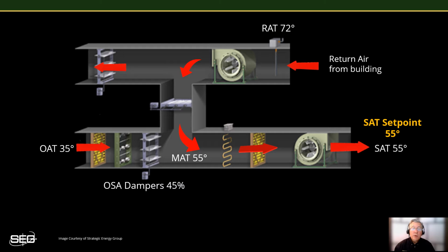And the system is performing properly per command, mixing the right amount of warm return air with cool outside air to maintain a constant supply air temperature of 55 degrees. Because this air handler utilizes what's called a fixed supply air temperature, the supply air temperature set point does not automatically adjust. If it needs to provide warmer or cooler supply air, it must be manually adjusted. Now, let's take a look at how simultaneous heating and cooling often happens even in a single path air distribution system like this.